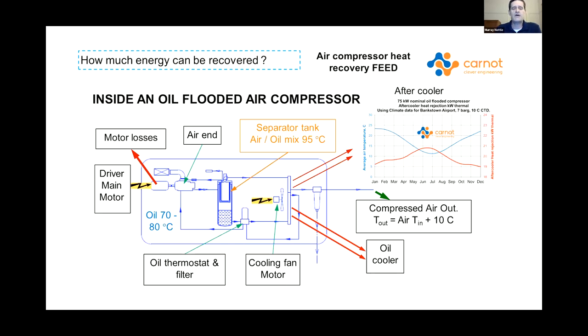Now, the oil going back in is kept at around 70 to 80 degrees, and the resultant separator temperature is kept up at 80 to 95 degrees. That is to stop water condensing in the system. So you can't overcool the system, or else you'll get water buildup in the oil and you'll rust out inside your machine. If you go too hot, the oil will break down very quickly and you can actually get separator fires and fires inside a compressor. So it's a bit of a balancing act. The compressor controls will shut down a machine. If it gets much above 95 degrees, it'll start to alarm and they'll shut down between 100 and 105, and that depends upon the compressor manufacturer.